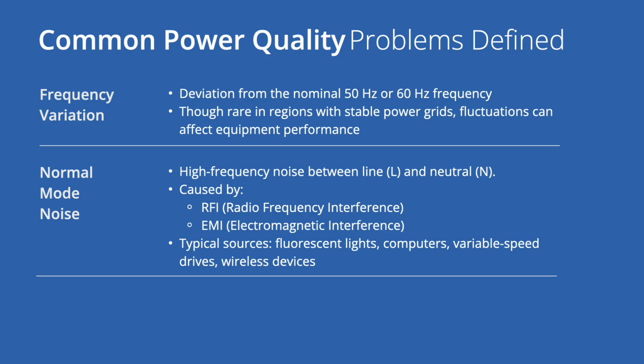Frequency variation, deviation from the nominal 50 Hz or 60 Hz frequency. Though rare in regions with stable power grids, fluctuations can affect equipment performance. Normal mode noise. High frequency noise between line and neutral caused by radio frequency interference, electromagnetic interference. Typical sources: fluorescent lights, computers, variable speed drives, wireless devices.